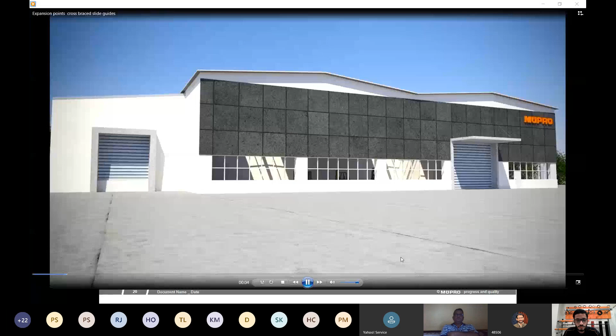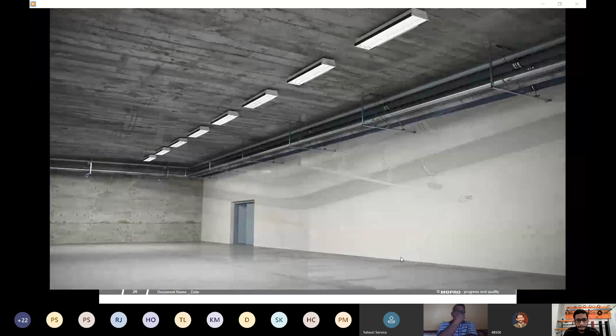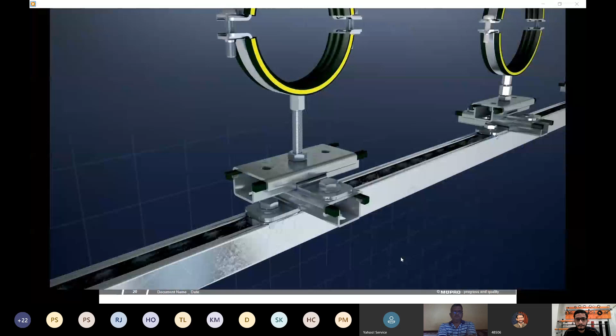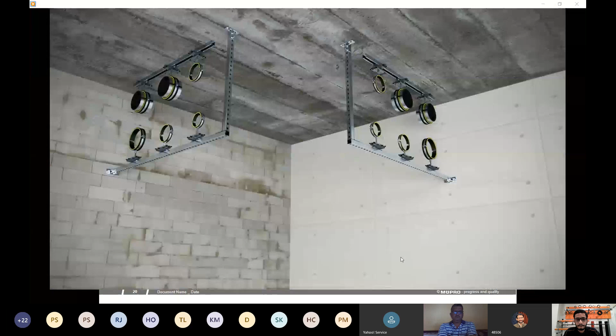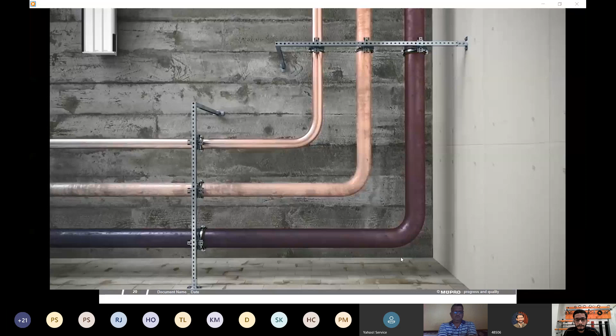For a safe fastening of pipe clamps, highly efficient and properly fixed anchor and expansion points are vital. MUPRO's fire-rated and efficient expansion points are tuned exactly to the needs of planners and users. Thanks to the assembly of a slide guide, single or cross-braced, the pipe can move flexibly in an axial and radial way. Why is this so important? Pipes change their length according to material, the medium flowing through them, and its temperature. This change in length must be considered to compensate tensions. A stable and a flexible fastening of the pipes is particularly important. Snapping or twisting of the pipes can result in expensive subsequent damages.